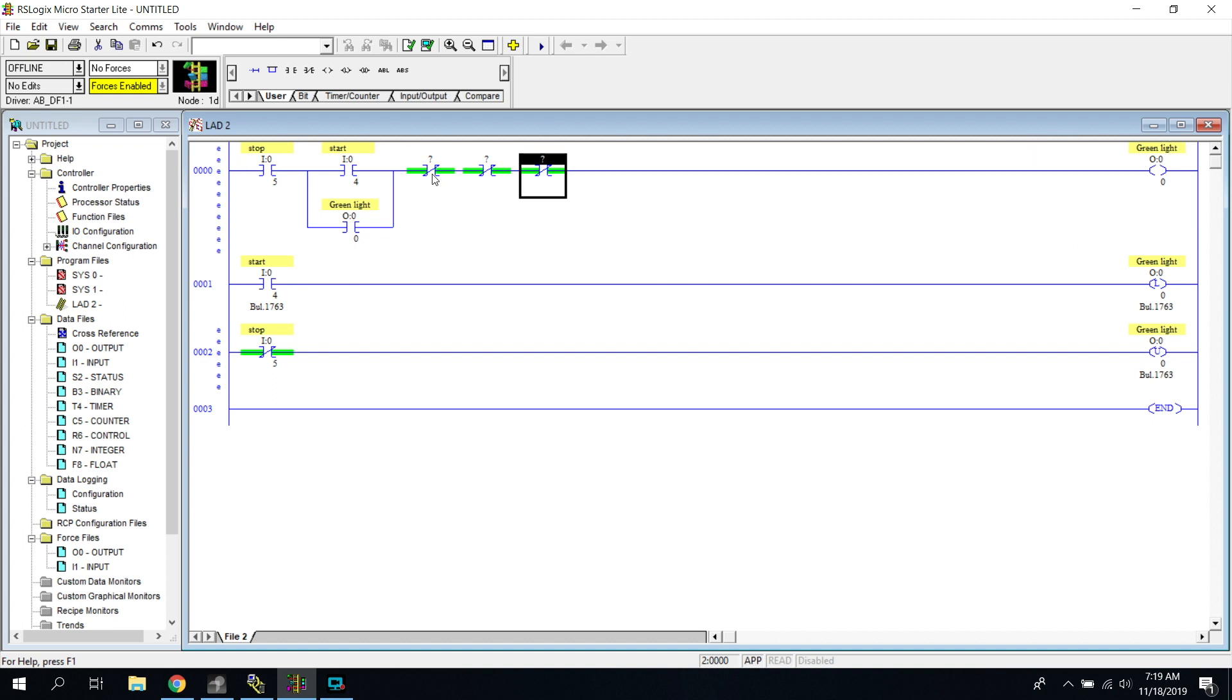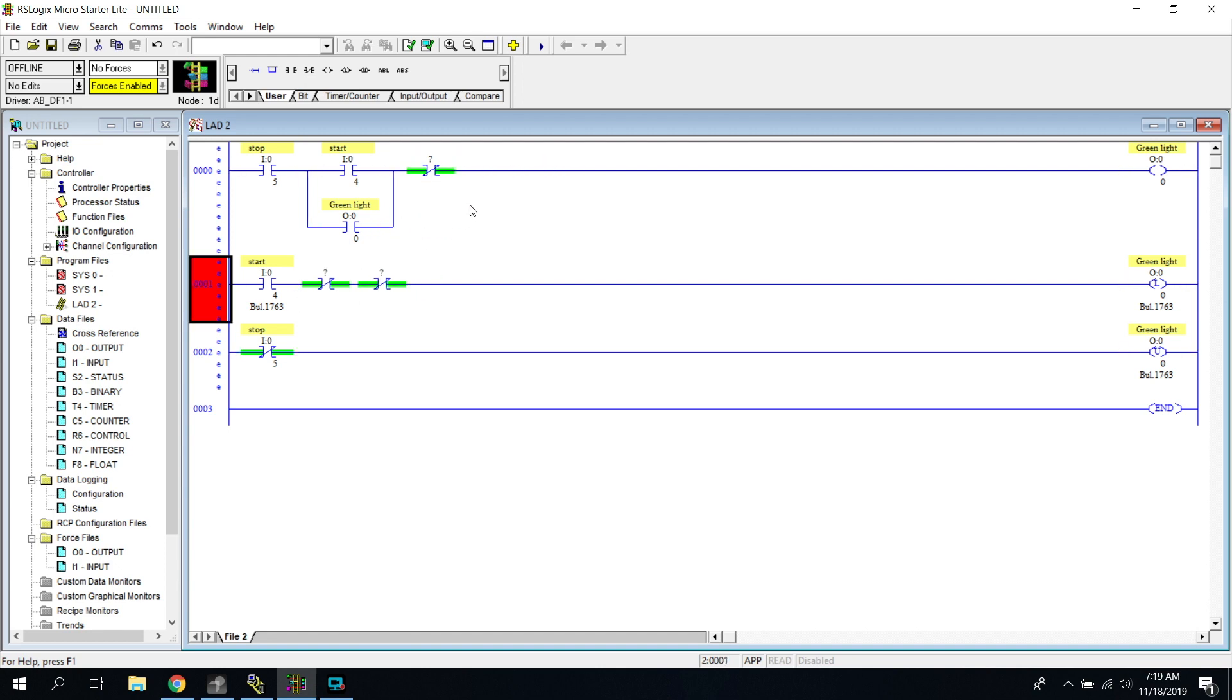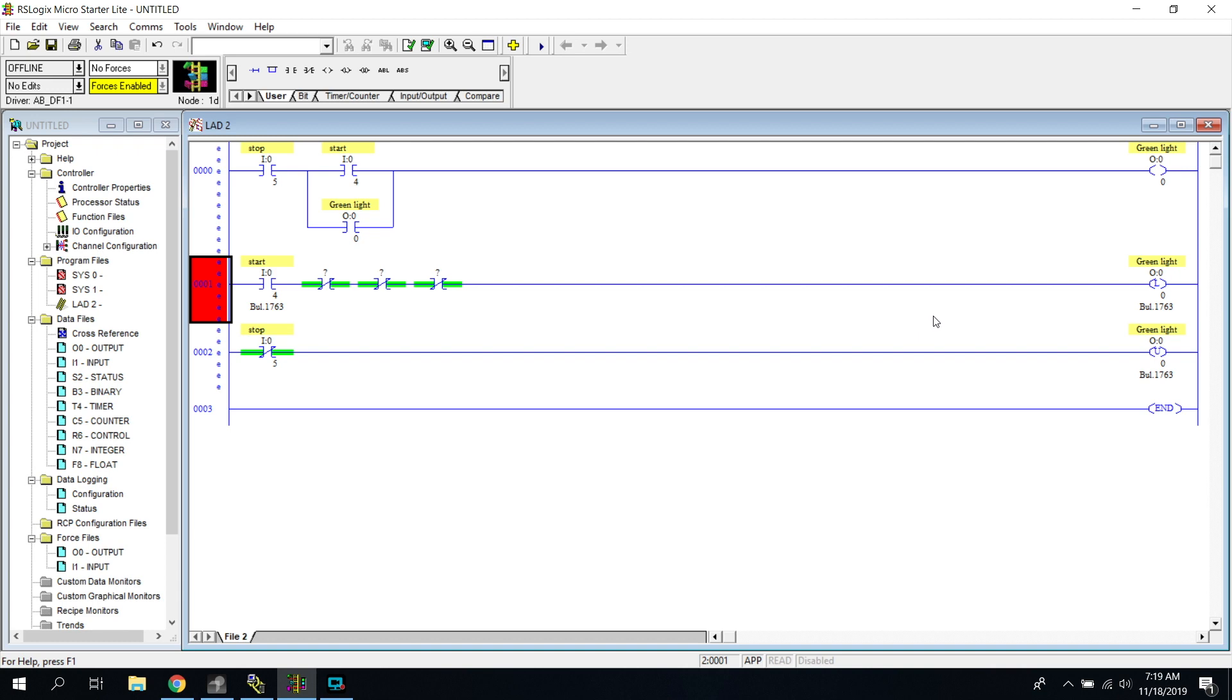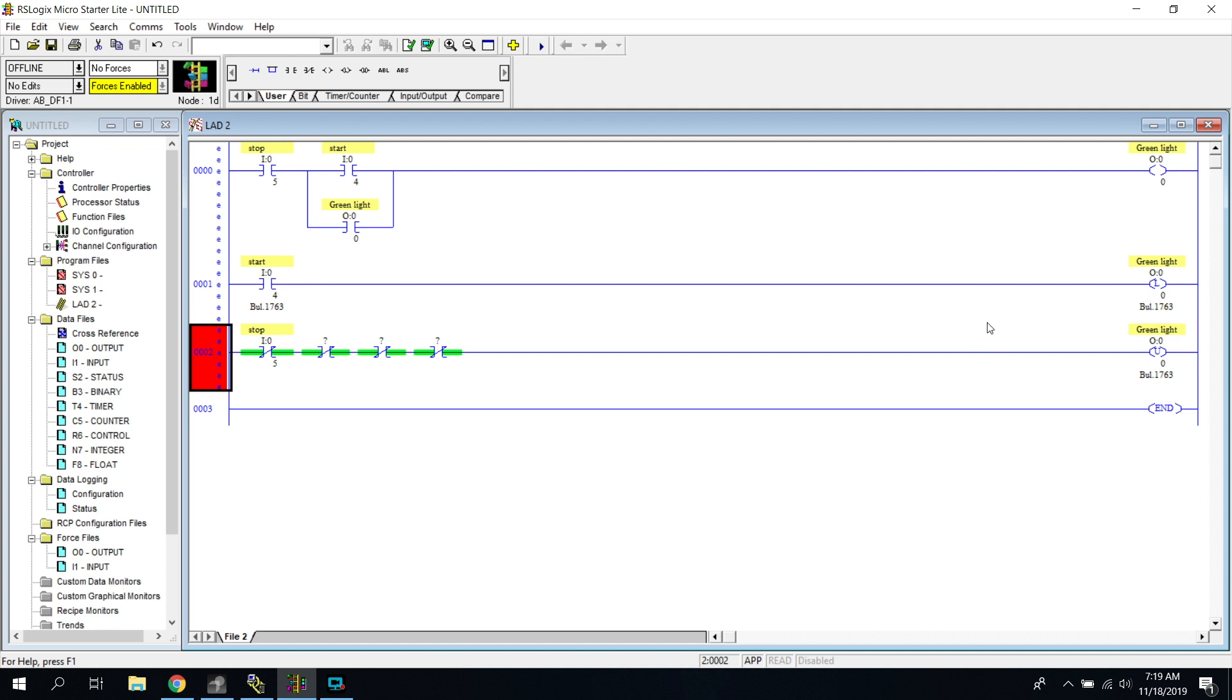Another thing is if we took this and we started putting in our different, let's say these were all limit switches and the limit switches were all, you know, one of them became false and then all three of them became true again, it's not going to latch or unlatch this bit. You would have to maybe put them down here, but again, nothing's going to relatch the start or this green light on. It's a little bit confusing because I don't know if that totally makes sense to you guys that this one would need to unlatch to turn off the light, but then we would need something to relatch the motor on or the light back on. So that's why these ones, this top rung is so useful.